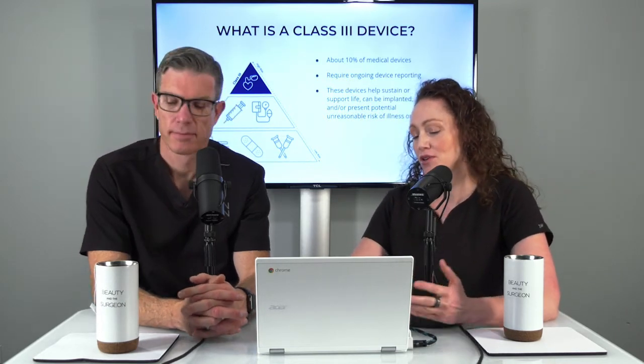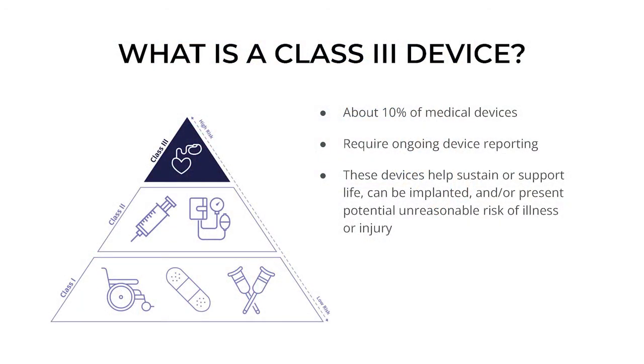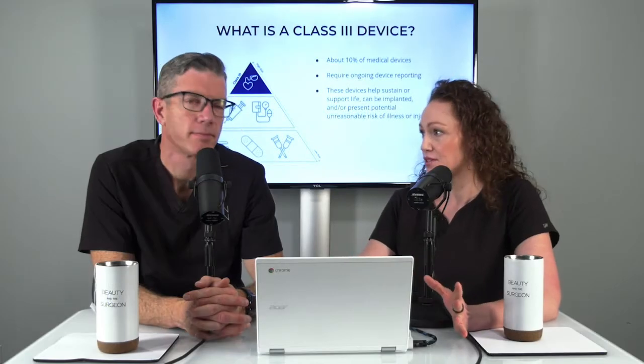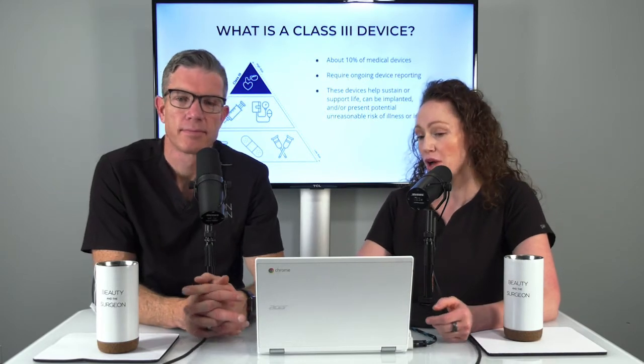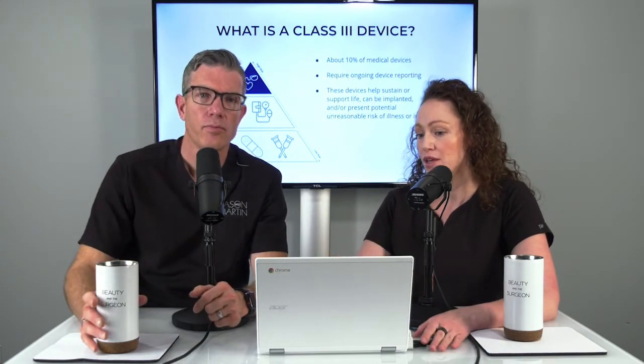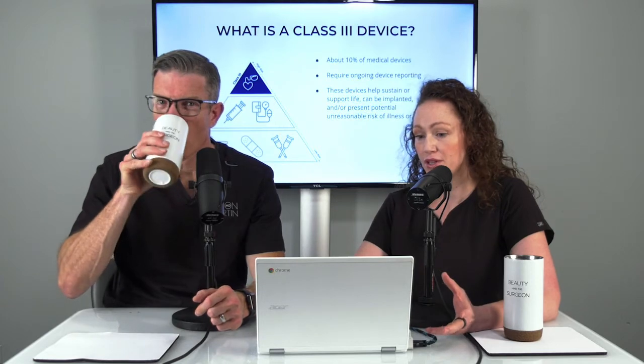Class 3 - the picture shows a pacemaker, so pacemakers, anything that's implanted, is a class 3 device. Class 3 is about 10% of all medical devices, which makes sense when you think that Band-Aids are in the bottom tier - there's a lot of stuff down there. They require ongoing device reporting, so for the history of the device, the FDA requires continual monitoring and continual device reporting. That's a unique thing to class 3.